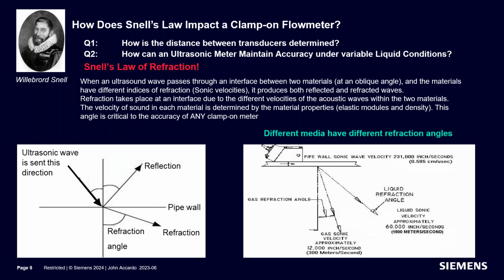What you can also see in the right picture is the transducer sitting on the pipe, and you see the arrow in the pipe wall pointing straight down the axis of the pipe. That is what we call axial beam injection, and it comes from the calculation of Snell's law relative to the pipe material, which in this case would be a steel pipe. The design of the transducer is influenced by this law from back in 1621, to ensure that when the beam enters the pipe wall, it refracts to 90 degrees and travels down the pipe wall, using the pipe as a waveguide, using its natural waveguide property. That conducts the beam over a very large area and radiates energy into the flow stream over a very large area. Hence the term wide beam that we developed back at the beginning of the flow meters in 1973.